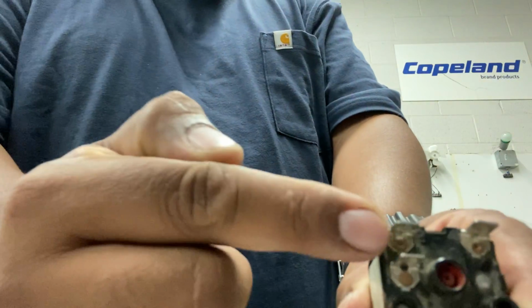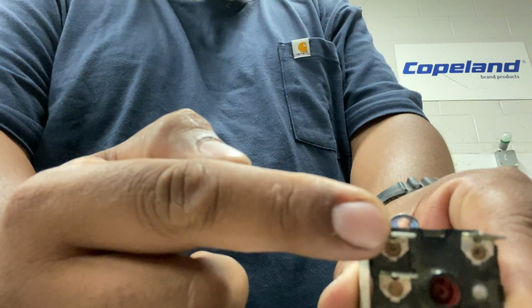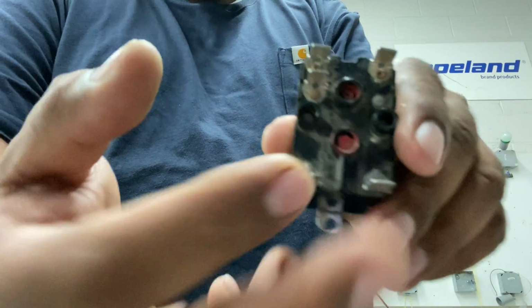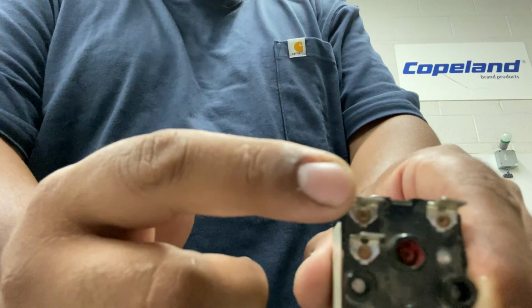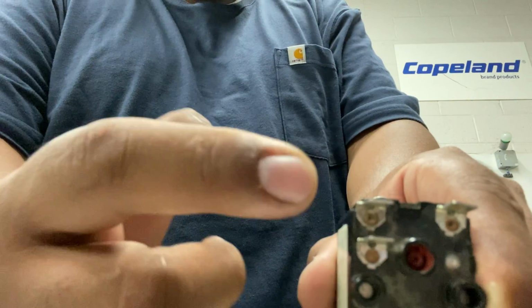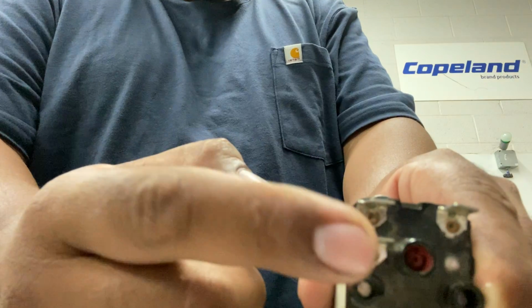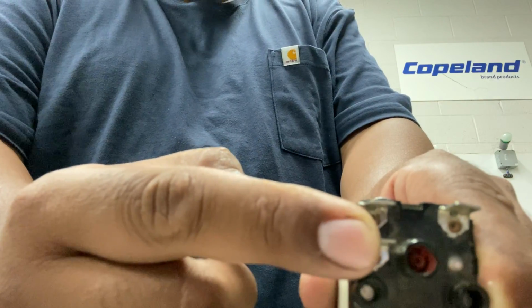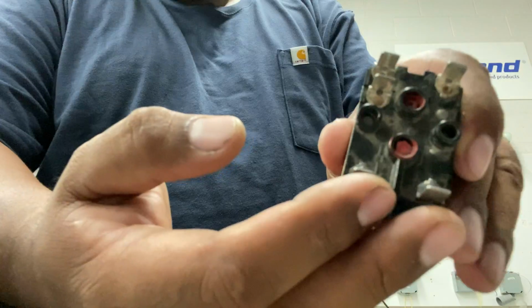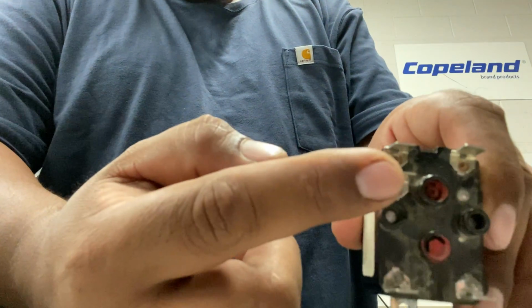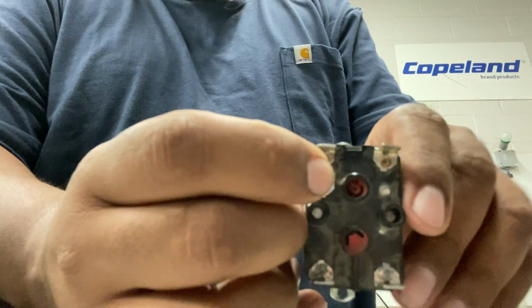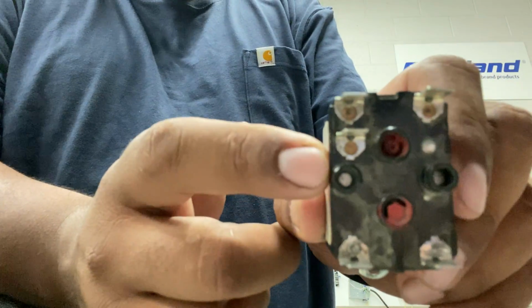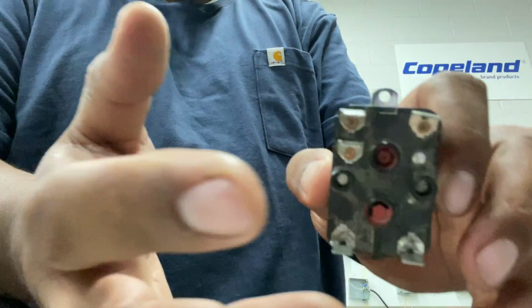The camera's not cooperating. But what it tells you is that if you hook up high power to pin number 2, when this unit is not running, meaning there's no 24 volts energized down here, between 2 and 5 is going to be active. So if you hook up 120 volts here, there's going to be 120 volts present down here. The minute you apply 24 volts down here, it will disengage pin number 5 and it will engage pin number 4. So this is a way we use relays to control equipment.